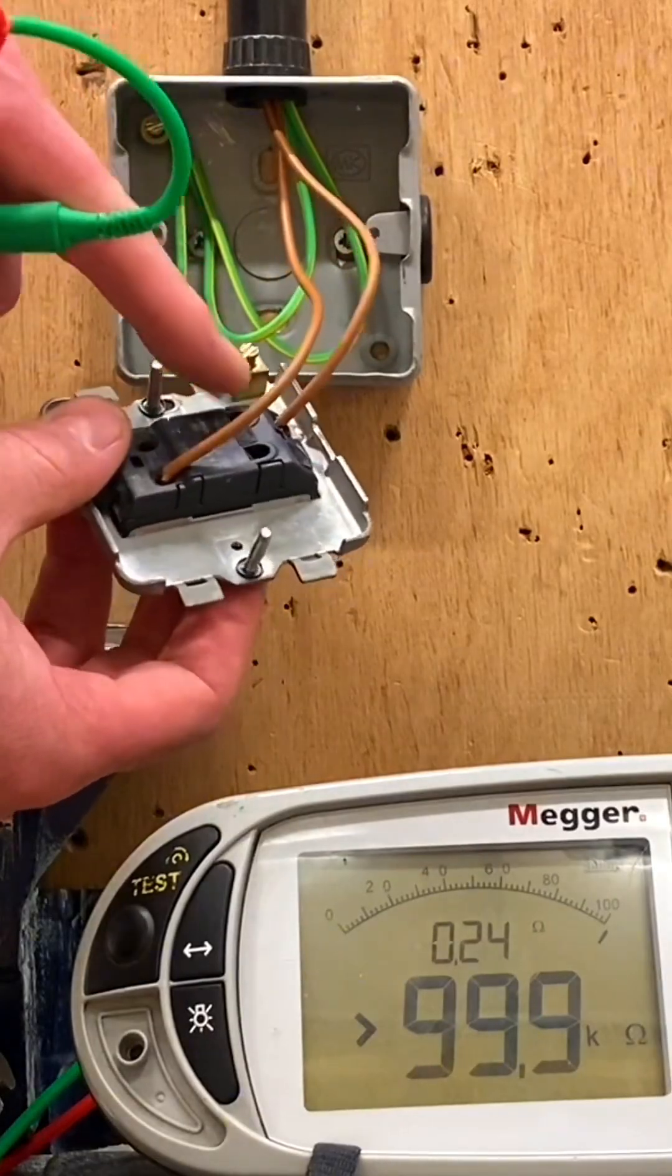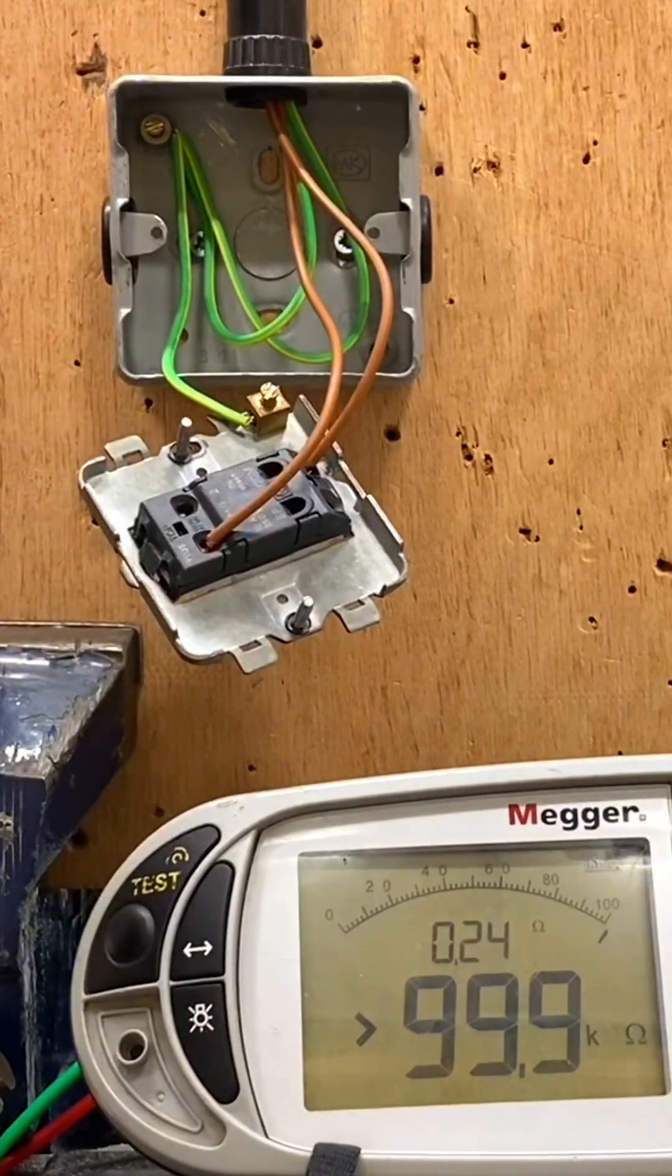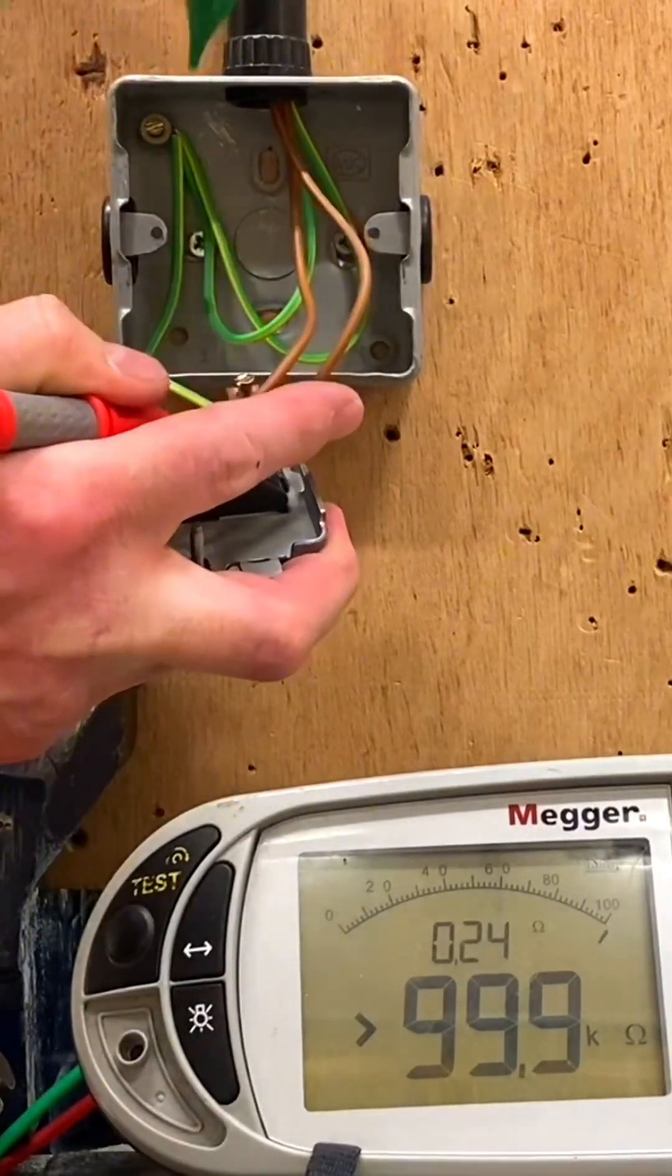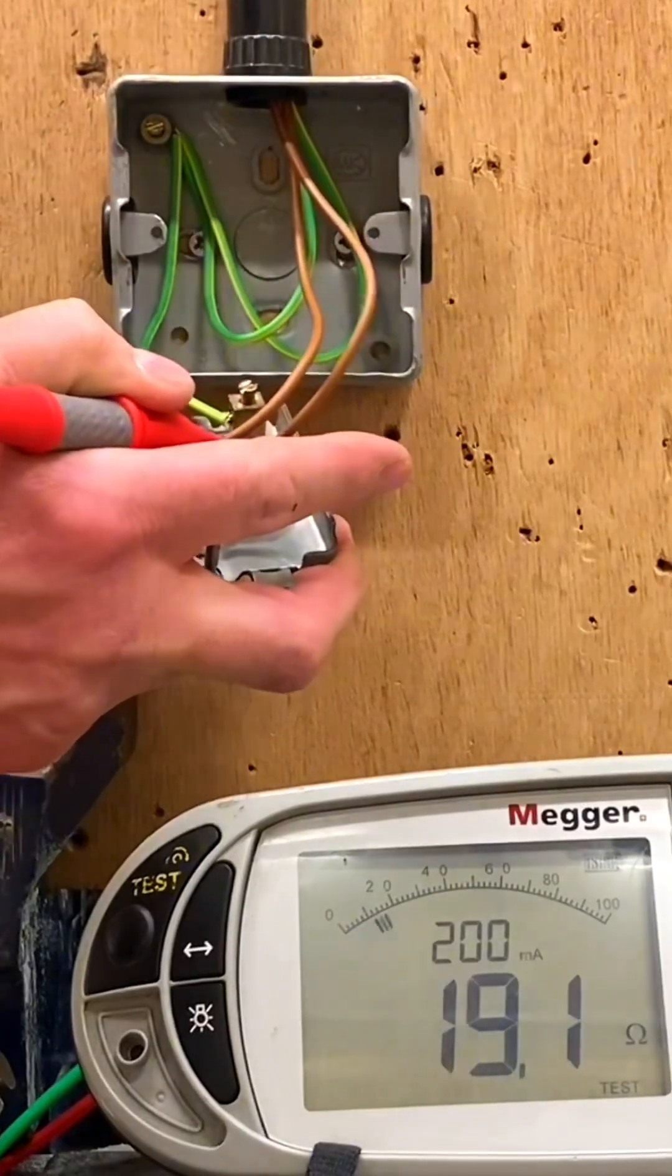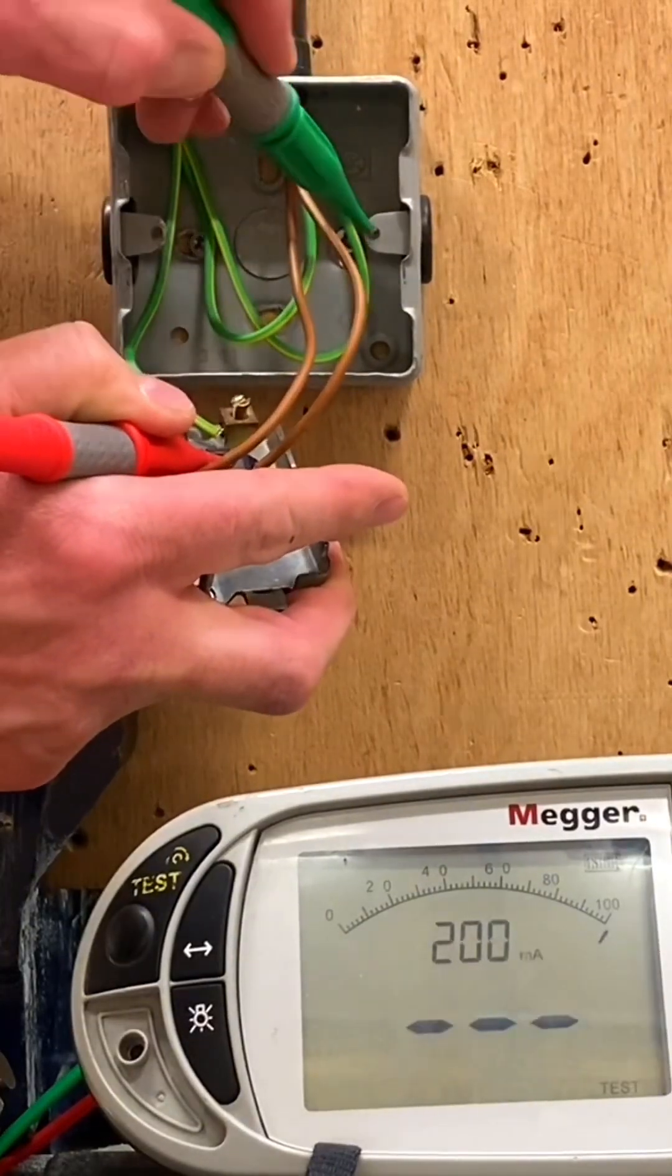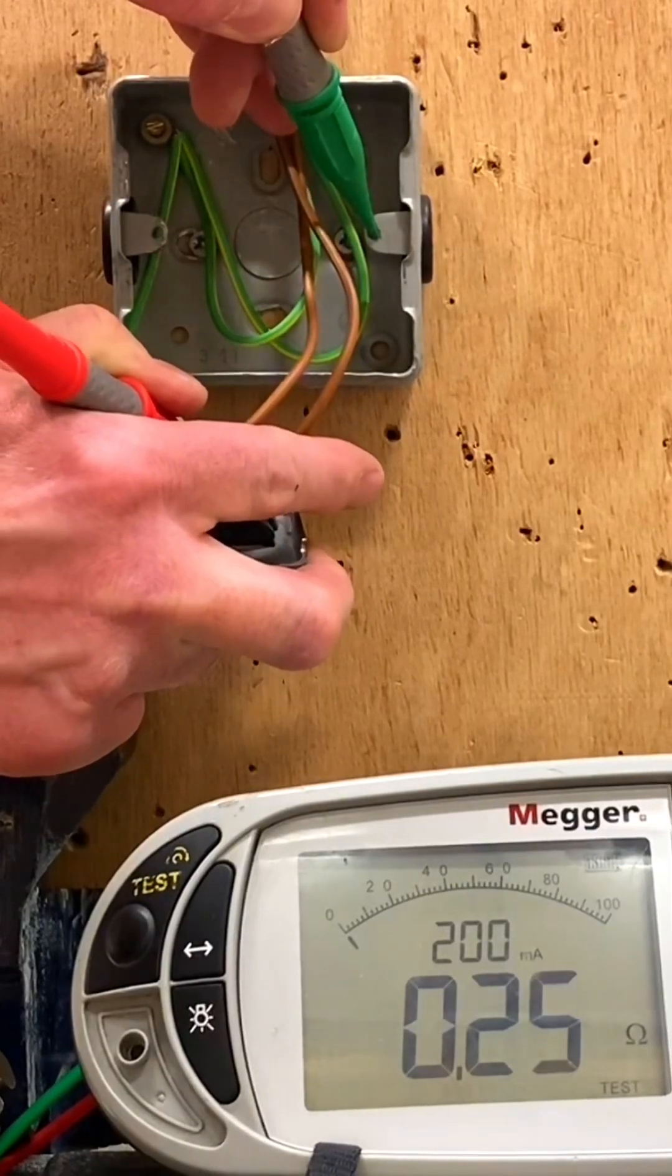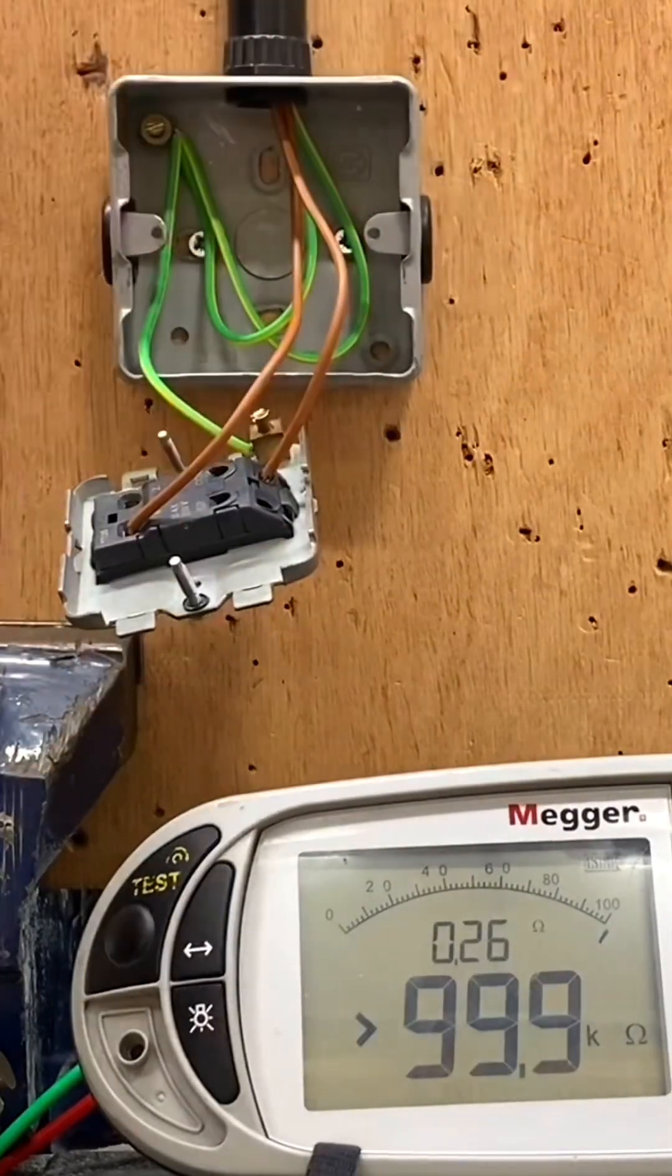Now going to the common of the back box - common here and into the back box, it's gone to the earth terminal, reading of 0.24. Then we're going to the threaded area of the screw and we get 0.24 again, 0.25 as it settles down. We've got to remember the highest reading there, so I got 0.25 of an ohm.